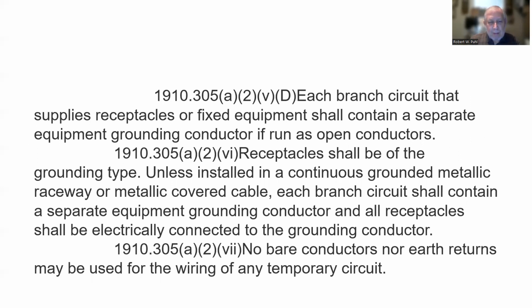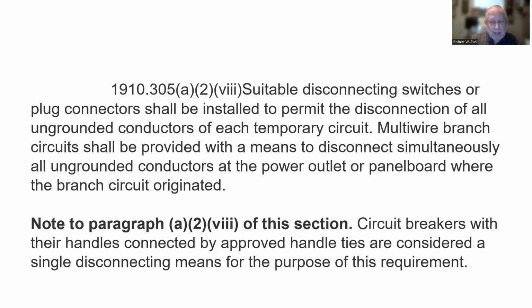Each branch circuit that supplies receptacles or fixed equipment shall contain a separate equipment grounding conductor if run as open conductors. Receptacles shall be of the grounding type unless installed in a continuous grounded metallic raceway or metallic covered cable. Each branch circuit shall contain a separate equipment grounding conductor, and all receptacles shall be electrically connected to the grounding conductor. No bare conductors nor earth returns may be used for the wiring of any temporary circuit. Now here they say earth returns, which is basically grounding. Suitable disconnecting switches or plug connectors shall be installed to permit the disconnection of all ungrounded conductors of each temporary circuit.